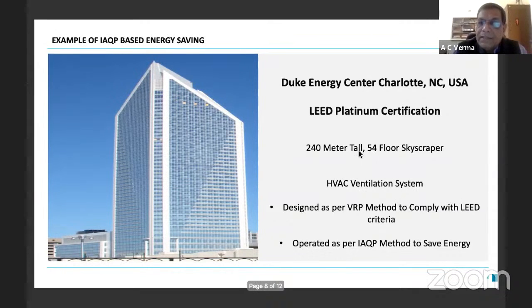The challenge was that the LEED version at that time, when this building was being designed 15 years back, had the provision that only the VRP method could be used. Though ASHRAE allows for the IAQP method, LEED did not allow it at that time. The consultants and client insisted they had to get LEED certification and also use IAQP. So the consultants found a way.